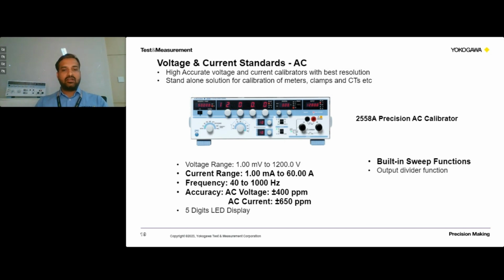It has an output divider function. That means we'll be able to source the value in terms of ratios like 1/4, 3/4, 1/15, 1/10, 2/10. Sourcing in ratios is critical for checking very critical applications such as current meters, current clamps, those kinds of CTs, where accuracy is defined for each step. So for those kinds of applications, this output divider function will be useful.